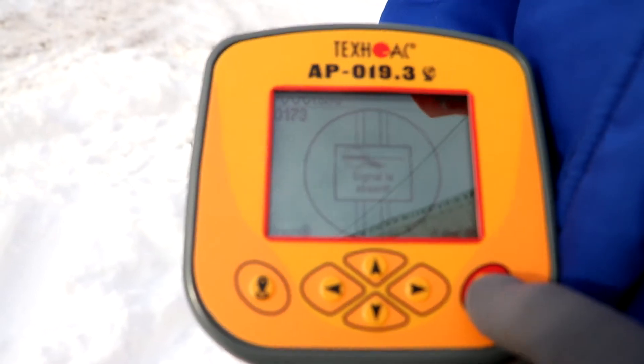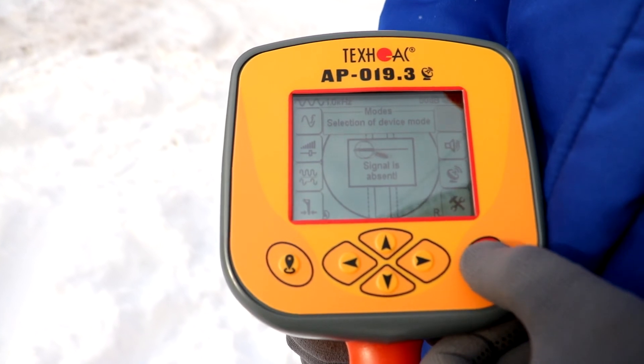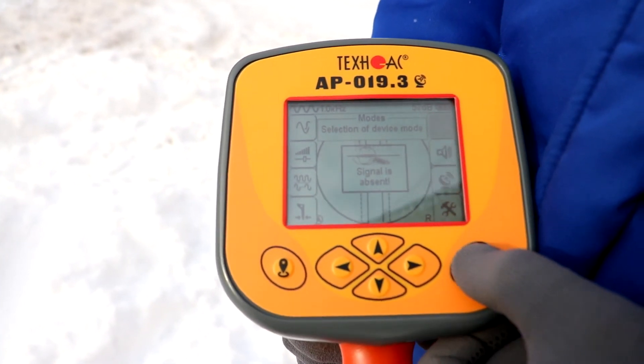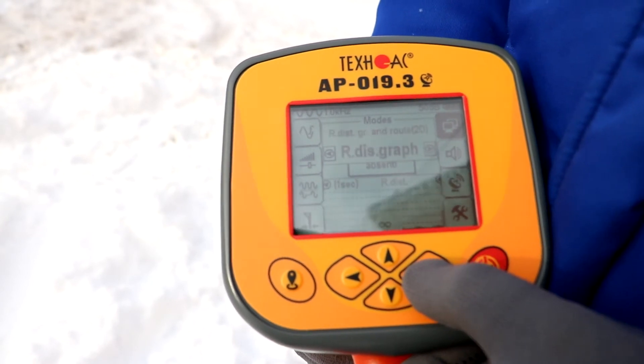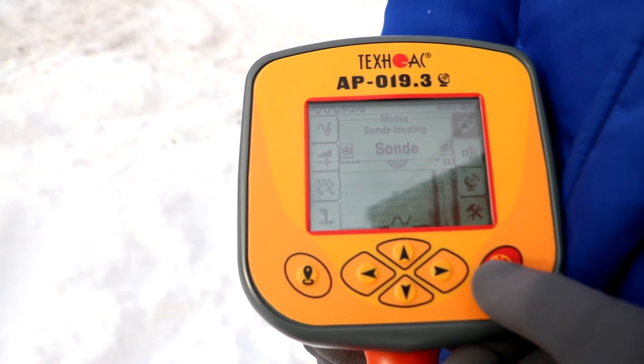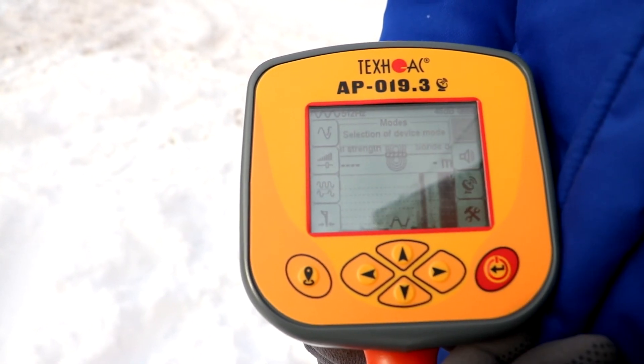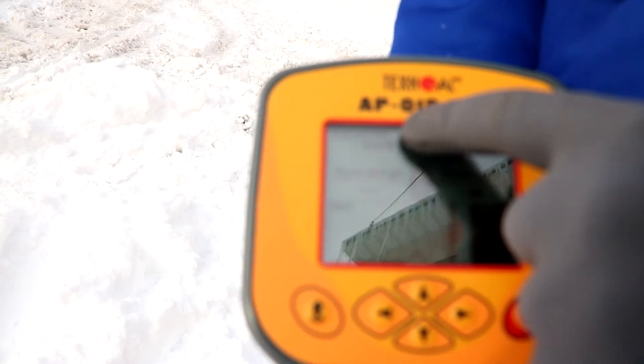In order to start the location of the sonde which is inside the pipe, we have to set the sonde mode. We turn on the menu of the receiver, then go to the menu and set sonde mode. We confirm our selection and the receiver is automatically set to 512 Hz, which is the frequency of the pipe transmitter.